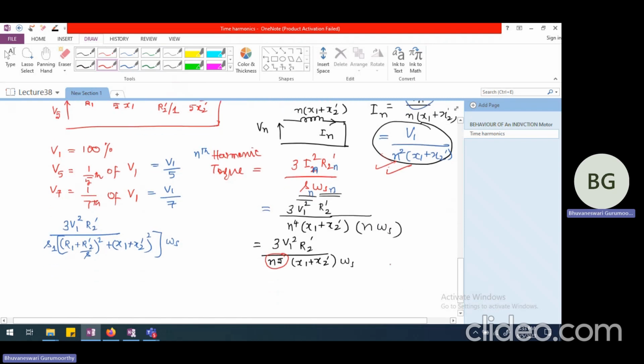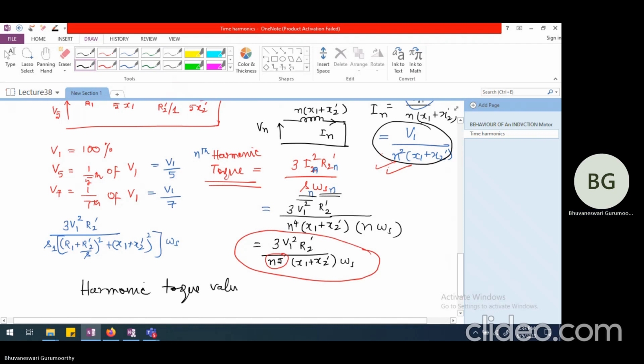So we might have to calculate this in case we are having a huge amount of harmonic voltages being applied to the induction motor. But even for a square wave, we are going to get a harmonic torque which is much, much less than the normal fundamental component of torque. So the conclusion is, even for a square wave voltage, harmonic torque values are negligible.